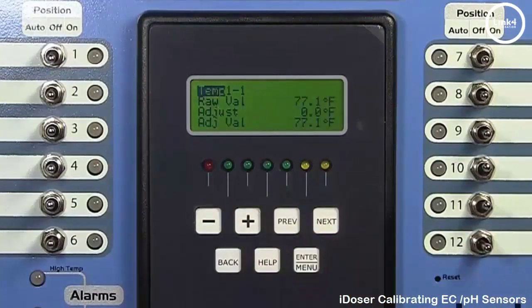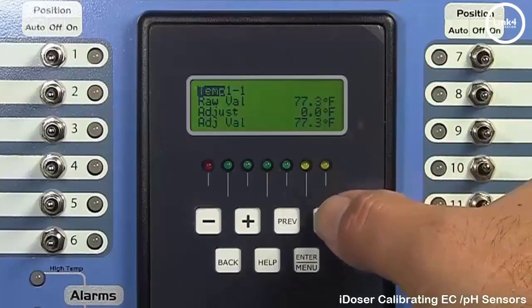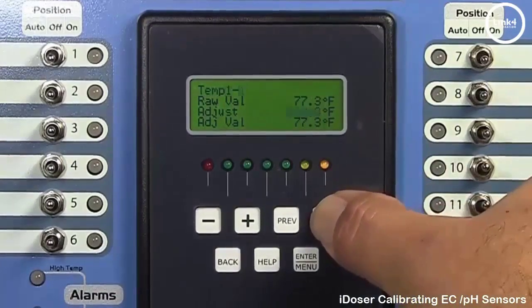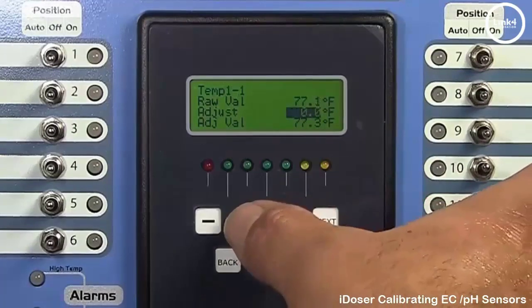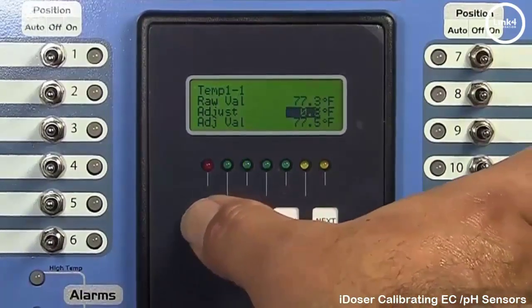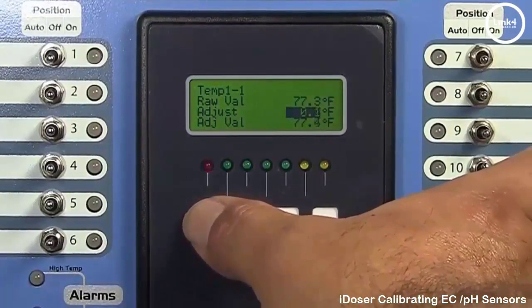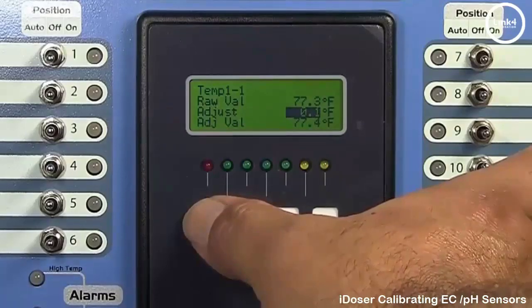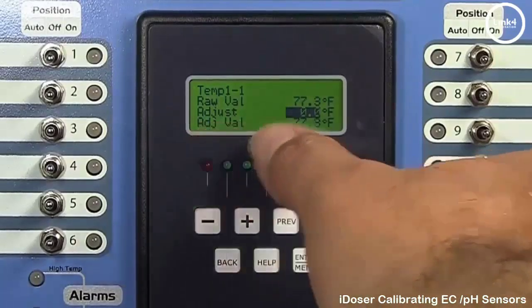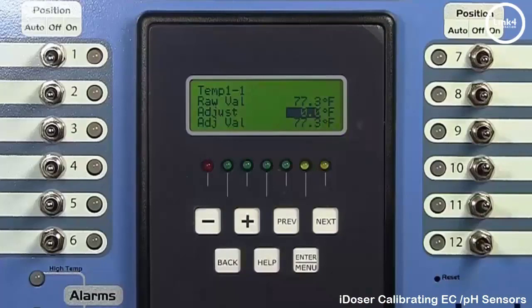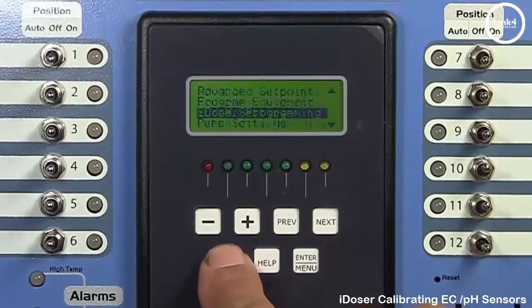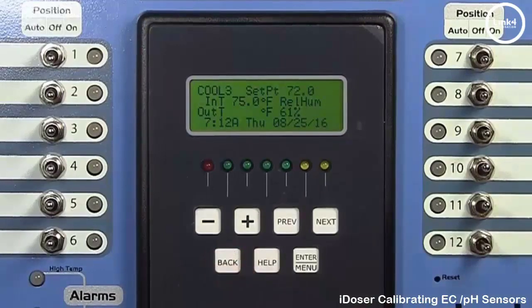The EC probe has a temp sensor built right into it. And if calibration for the temp is necessary, we would do it in this field, by simply going to the adjust line and hit plus and minus to make the raw value increase and decrease, which will display the adjust value at the home screen. So we're going to leave it at 0, hit back to save your changes.